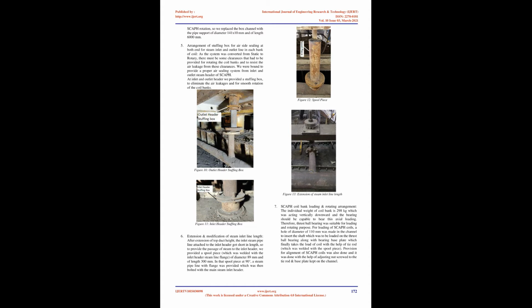Lastly, it was decided to turn the static SCAPH into a rotary SCAPH so that when not in use it remains parallel to the airflow path without causing any restriction in the air path, and thus the system resistance will automatically get eliminated without sacrificing the benefits of SCAPH to prevent cold end corrosion during peak winters or startups.